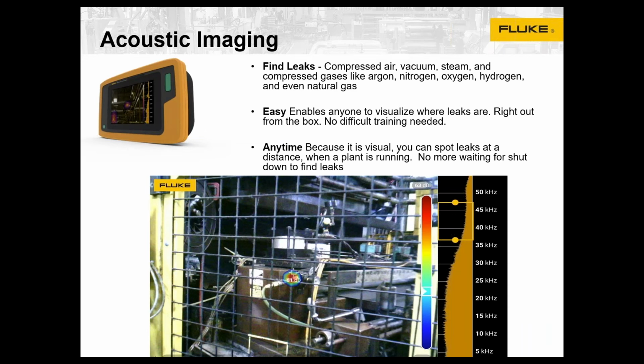As mentioned, it's primarily for finding leaks, which could be in compressed air systems. It can also find not just pressurized leaks but vacuum leaks, and other types of gases. Could be high pressure steam, which might be a safety consideration, or other gases you as a company might need to pay for, such as welding gases, argon, nitrogen, oxygen, hydrogen, CO2, and even natural gas. We'll take a look at some example images taken with acoustic imaging of a variety of gases on a later slide.